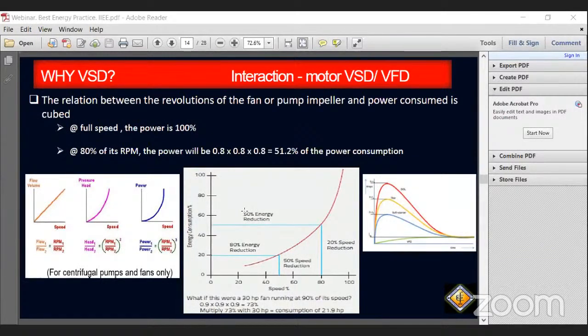You can see the graph, the fan and impeller curve on the right side, power versus speed. Power is proportional to the cube of the speed. So at full speed, the power is 100%. But when you lower your RPM, your speed, example 80%, the power will be the cube, 0.8 times 0.8 times 0.8, that is 51.2% of the power consumption. The middle presentation represents the energy consumption versus the speed.